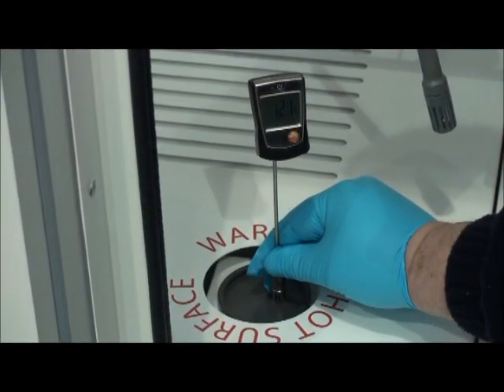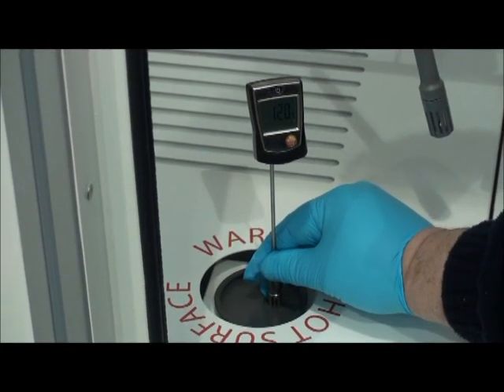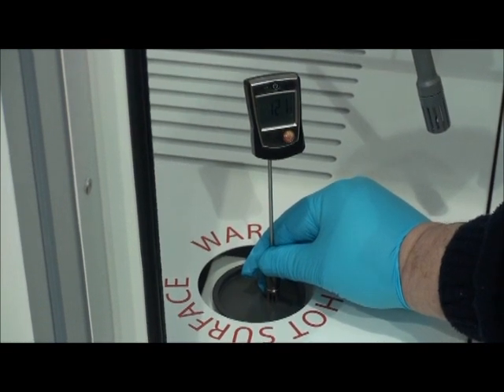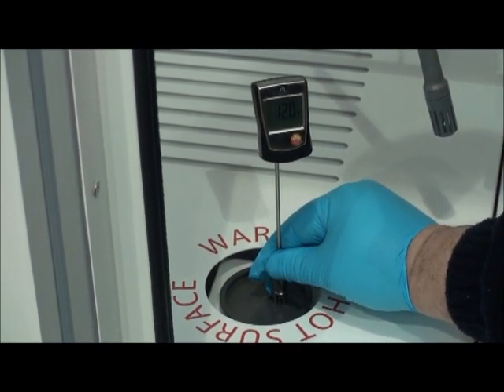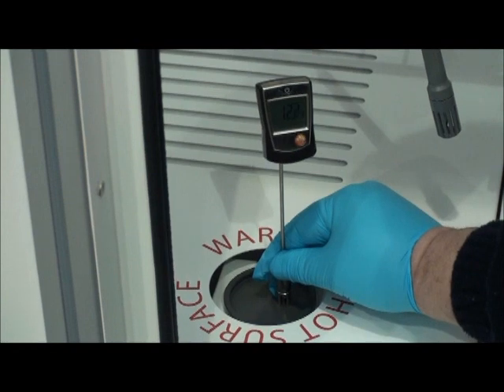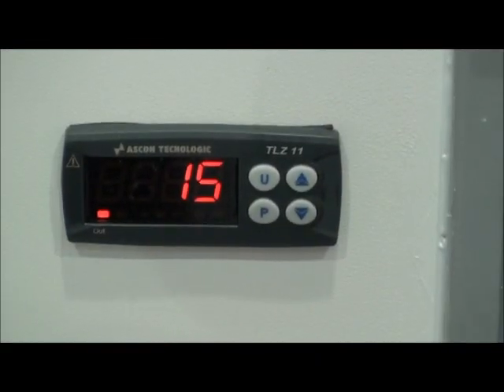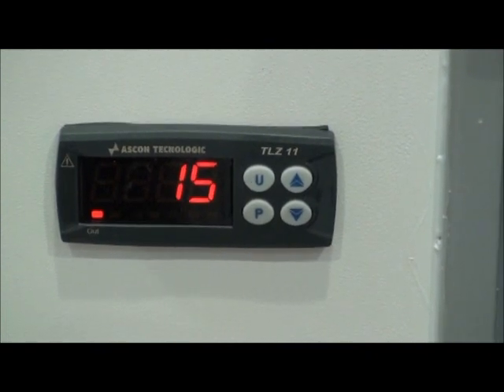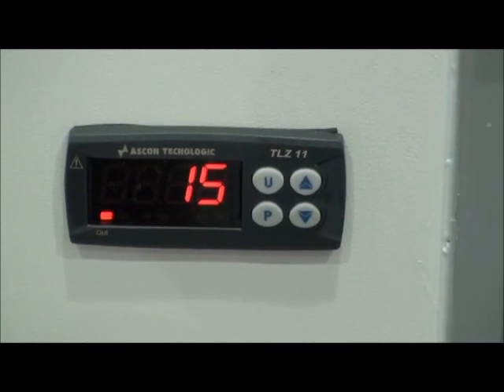To calibrate the hot plate, using the hot plate probe, I measure it now when it's cold, and I've got 12 degrees. The display is reading 15 degrees, which is within the specification.